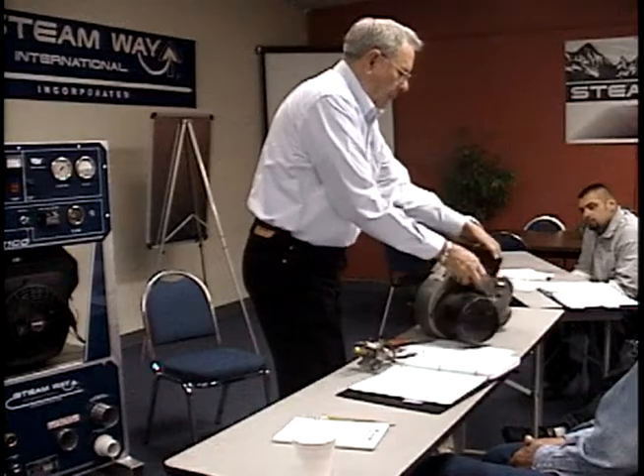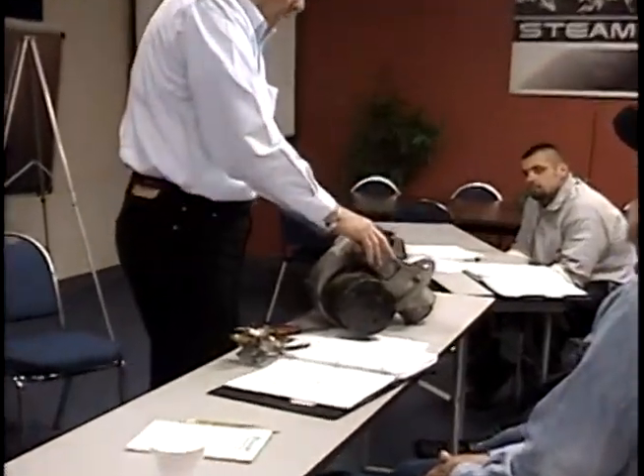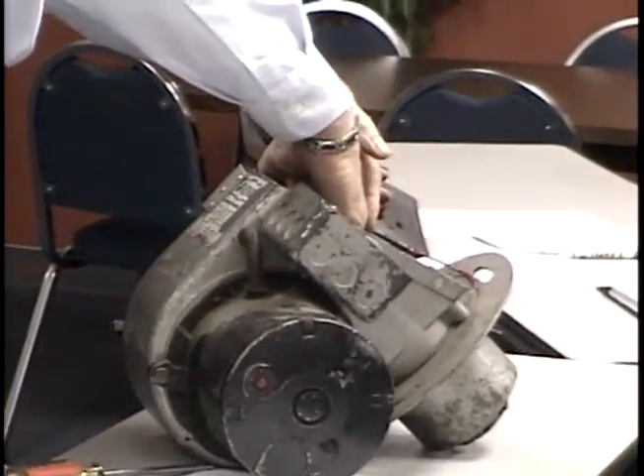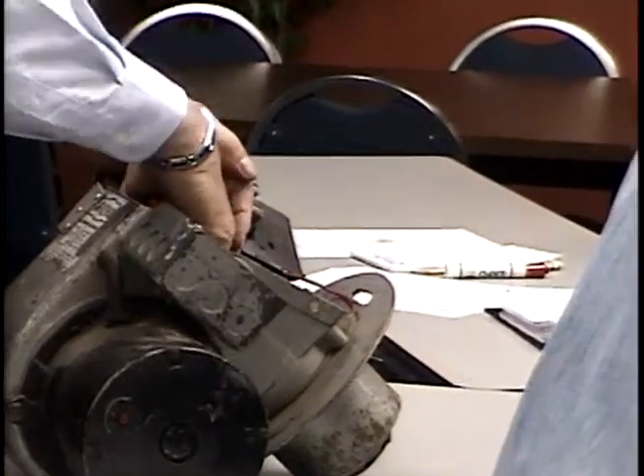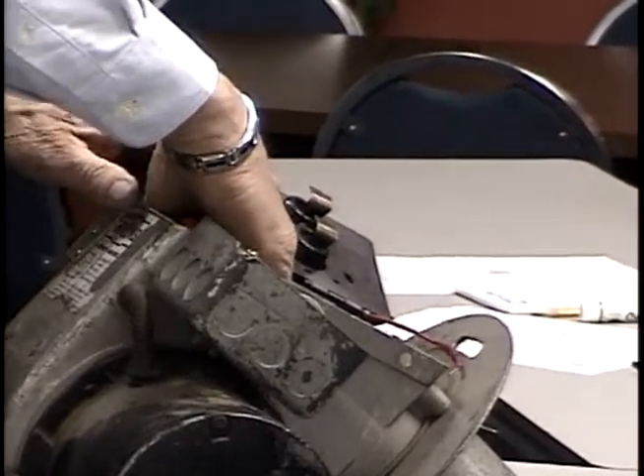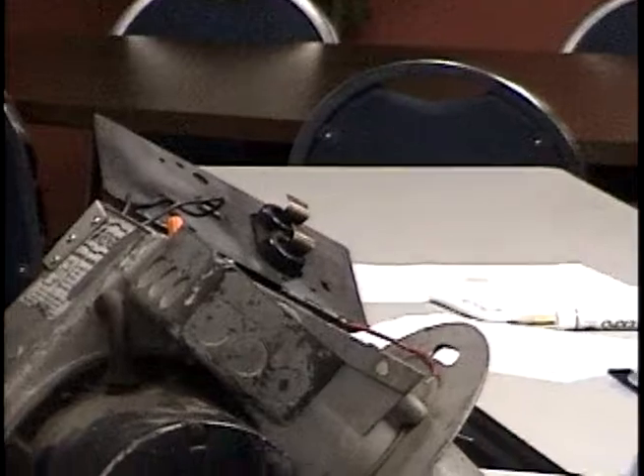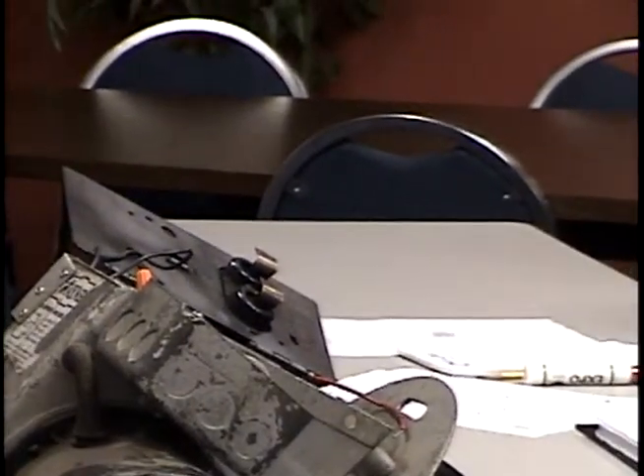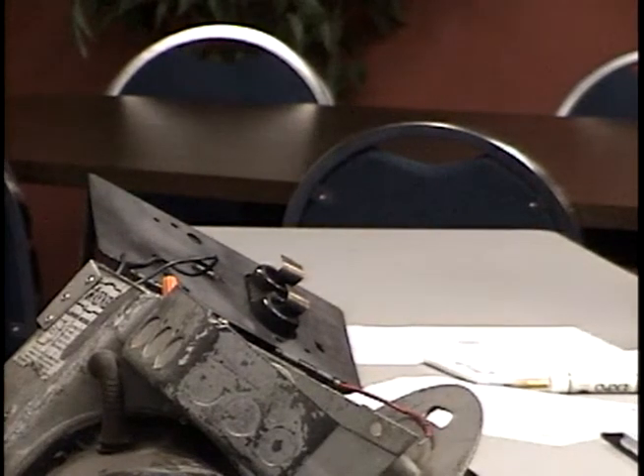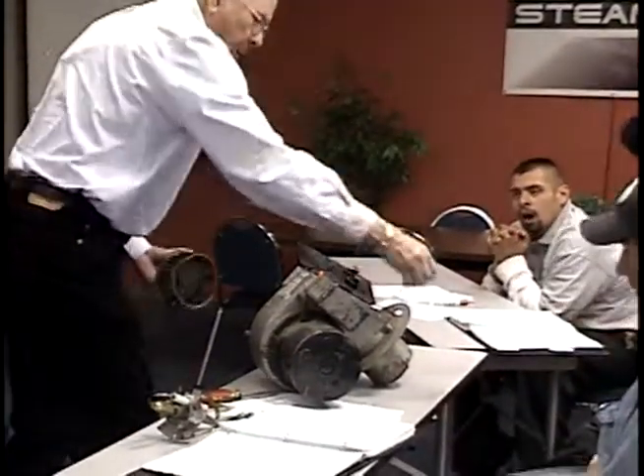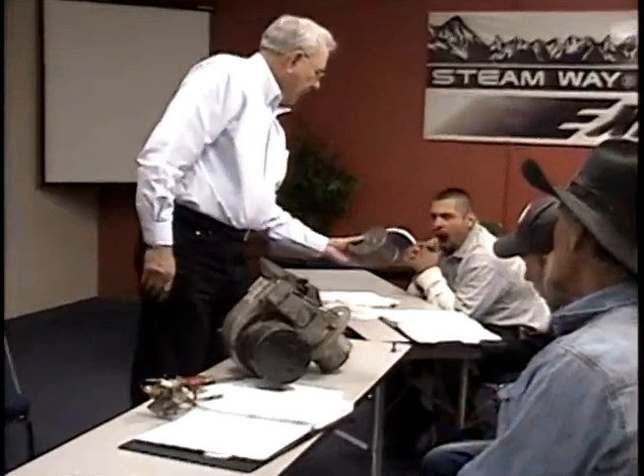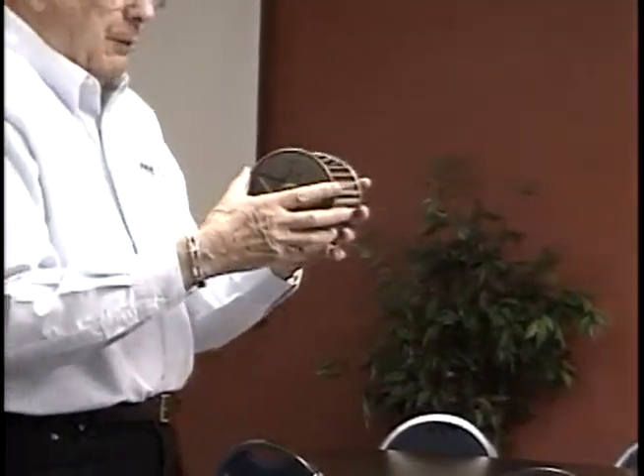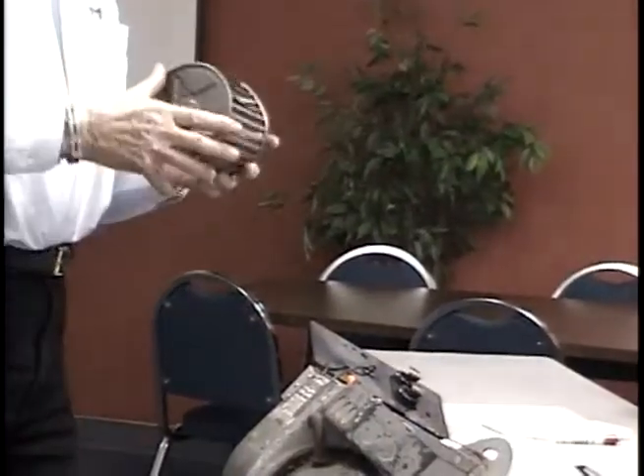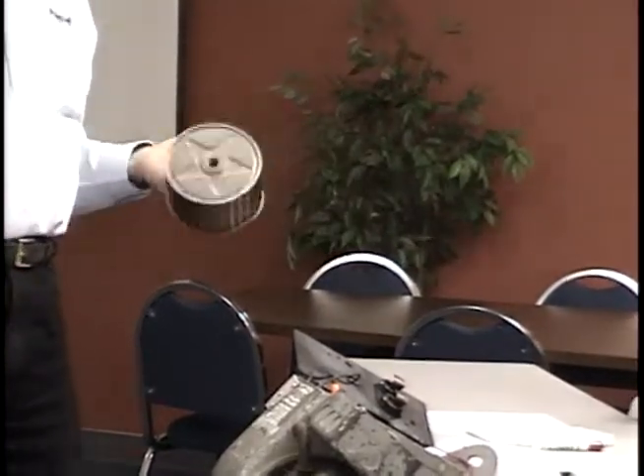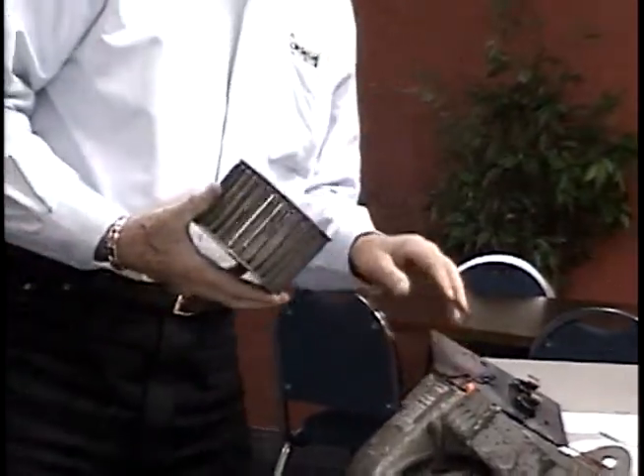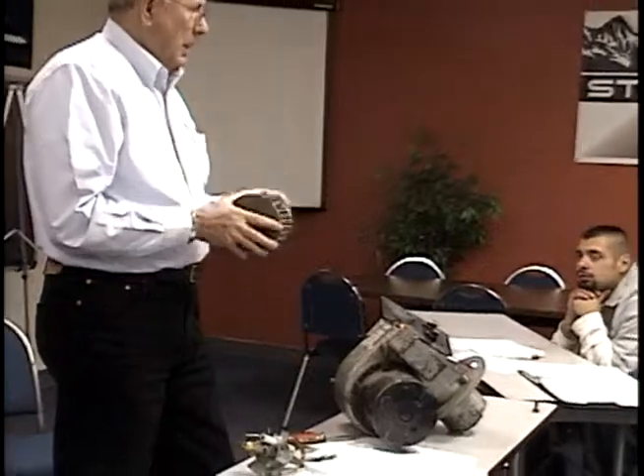In this case, what you probably would do, you would open this transformer, power off, reach in and with your pinkies, don't put a screwdriver in there, rotate the fan until you break it loose. You got more power than this little 1/4 horsepower motor. So normally you can break it loose just by turning that fan. The fan looks something like this, and there's a hollow bolt that I'm talking about that holds it on. But see, somebody has played a little game with that, and it turned at 3,450 RPM. If I stuck this on here, guess what would happen? It would shake itself. It'd be worse than your tire on your car that's way out of balance. It'll shake the burner system apart. So try not to bend the blade. That's the reason they do it with your pinkies if you need to.